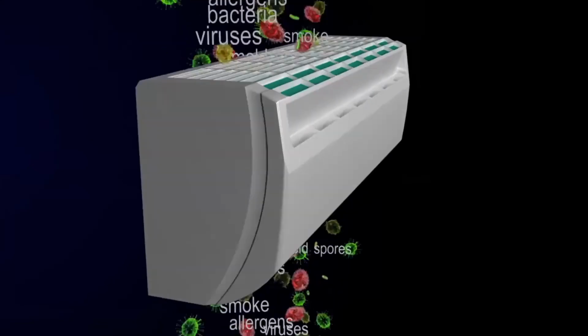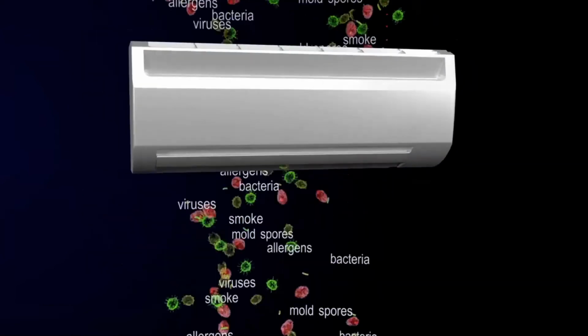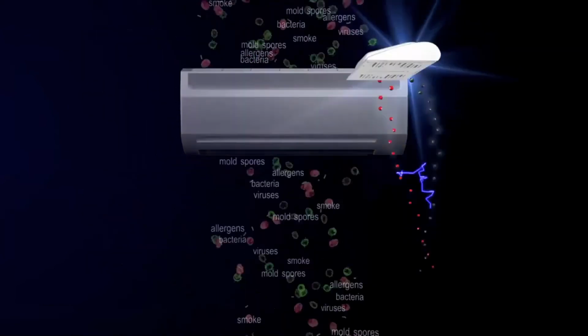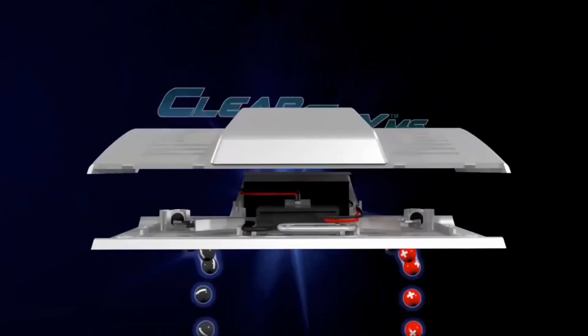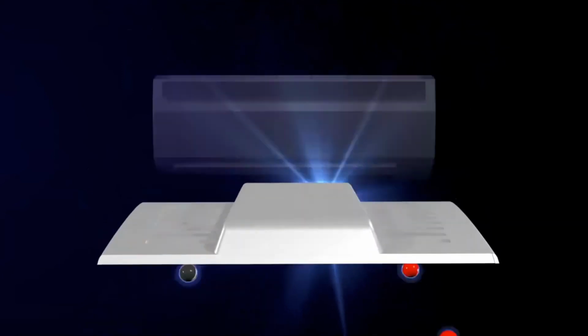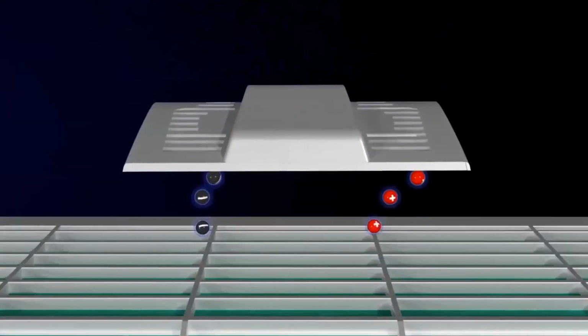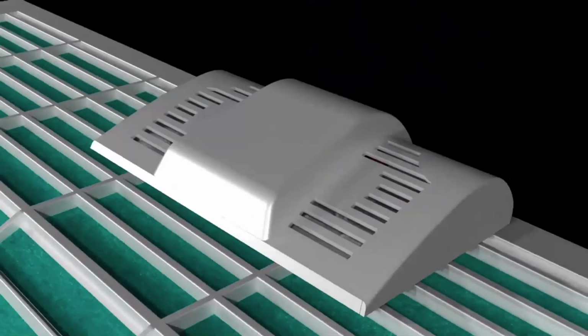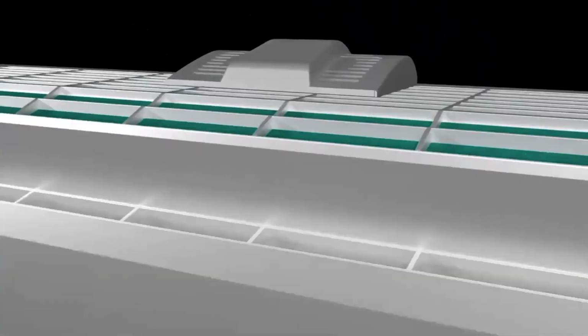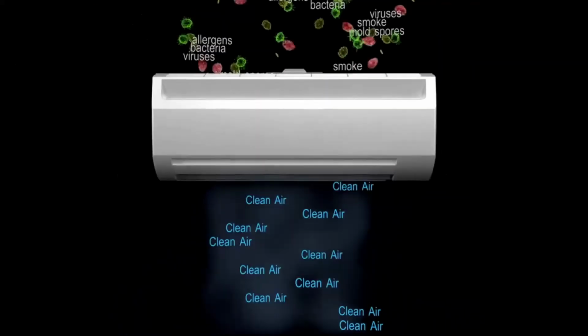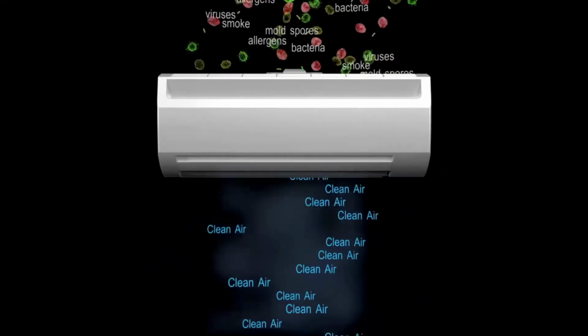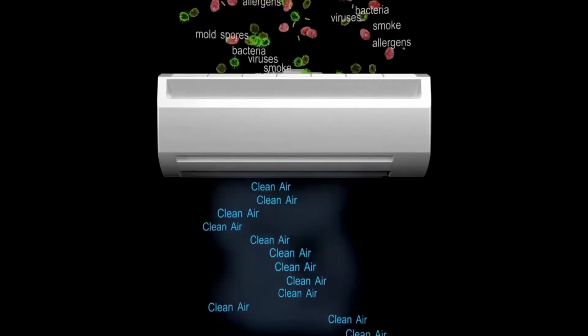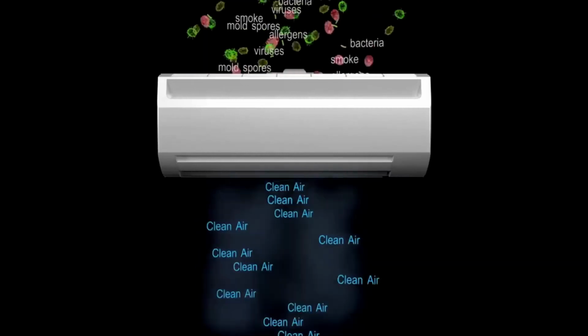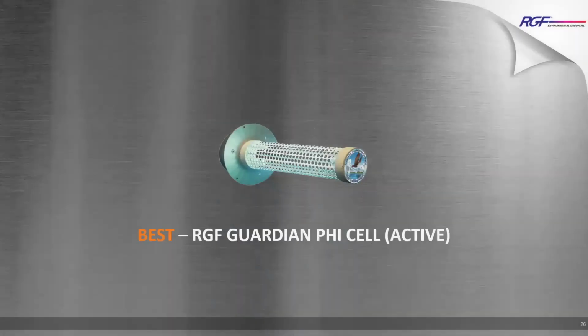So you can see right here, this is your evaporator—everyone knows this, this would be, for instance, a Holman's Mitsubishi evaporator hung on the wall. Clear Sky is a self-cleaning ionizer that we provide, and this mounts to the very top of the evaporator head. So what you're doing is really twofold: you're cleaning the evaporator core of viruses and mold, especially mold because that can tend to group on it, but you're also, on the downstream side, cleaning the air proactively as it goes out into the occupied space. So the ions are distributed through the evaporator core and then also into the occupied space.